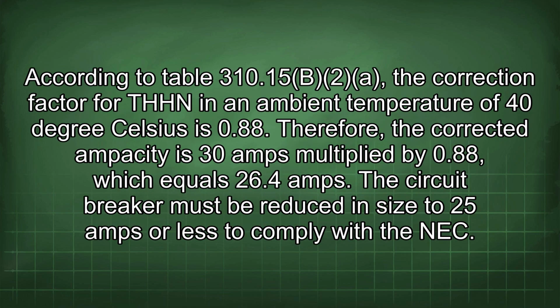According to Table 310.15(B)(2), the correction factor for THHN in an ambient temperature of 40 degrees Celsius is 0.88. Therefore, the corrected ampacity is 30 amps multiplied by 0.88, which equals 26.4 amps. The circuit breaker must be reduced in size to 25 amps or less to comply with the NEC.